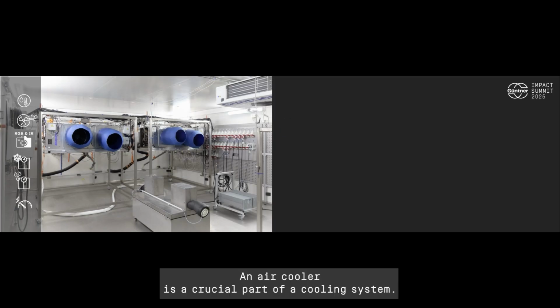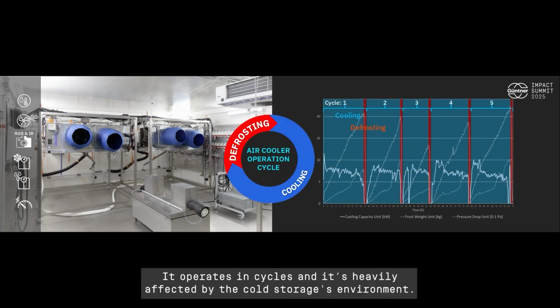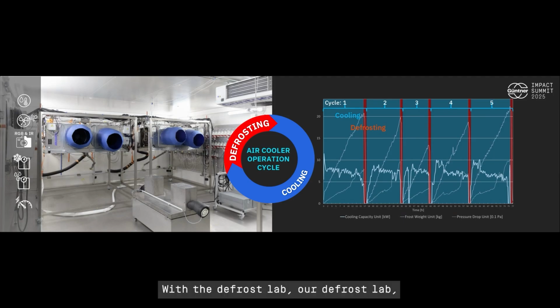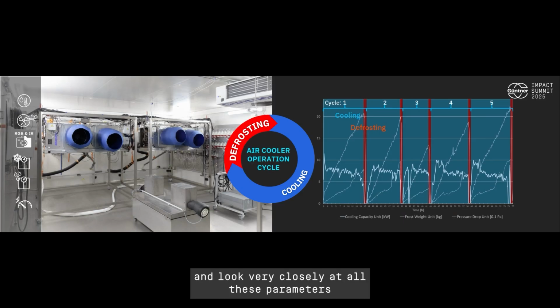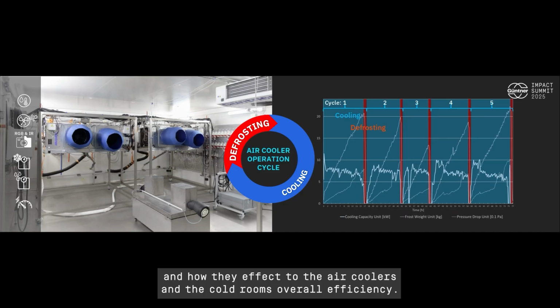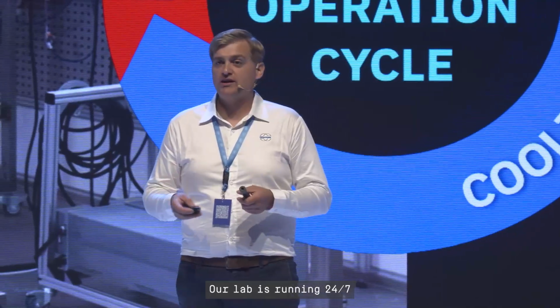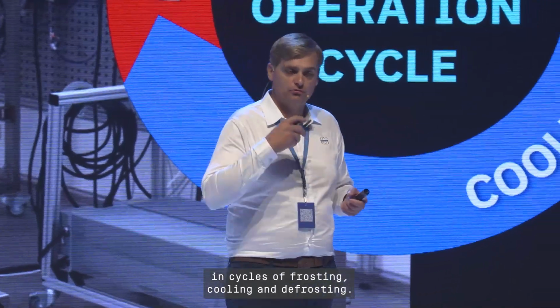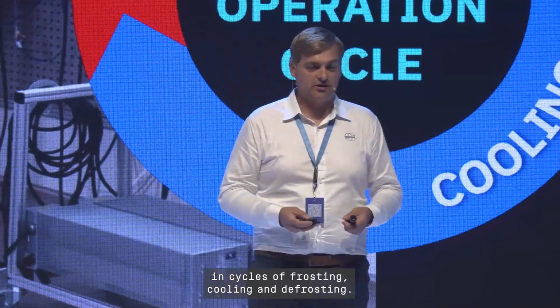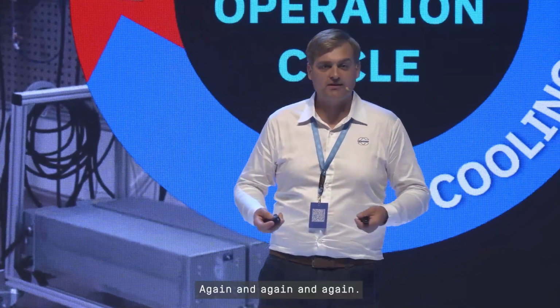An air cooler is a crucial part of a cooling system. It operates in cycles and is heavily affected by the cold storage environment. With our defrost lab, we are operating our air coolers in real-world cold room conditions. We control every single parameter and look very closely at how they affect the air coolers and the cold room's overall efficiency. Our lab is running 24/7 in cycles of frosting, cooling, and defrosting, again and again and again.